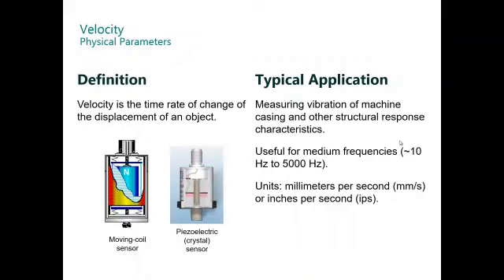Velocity is the time rate of change of the displacement of an object. There are two different sensors: moving coil sensor or piezoelectric or crystal sensor. Typical application is vibration of machine casing or other structural response. The useful frequency is 10 to 5000 hertz. For the moving coil, the maximum frequency is 1000 hertz. The measurement is millimeters per second or inches per second peak, also referred to as IPS.